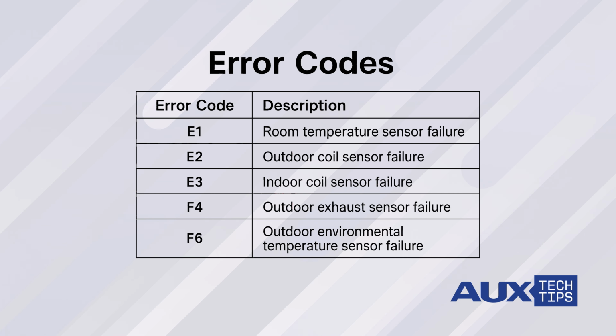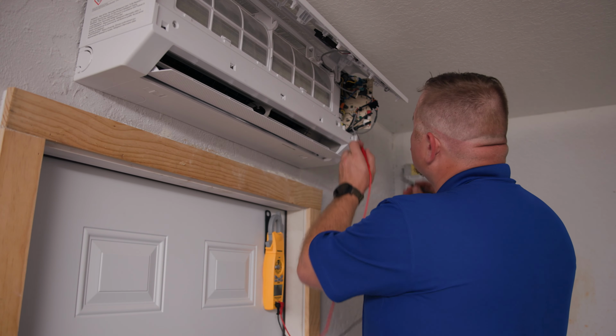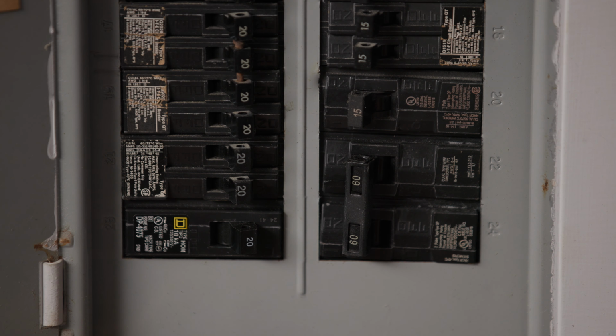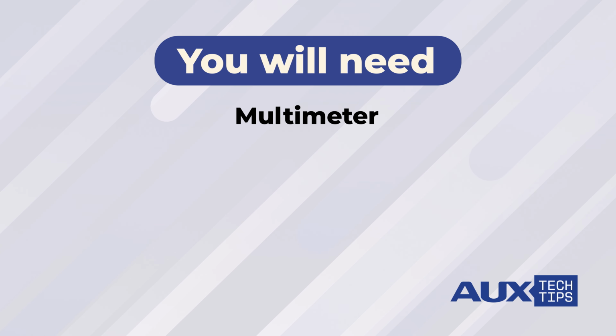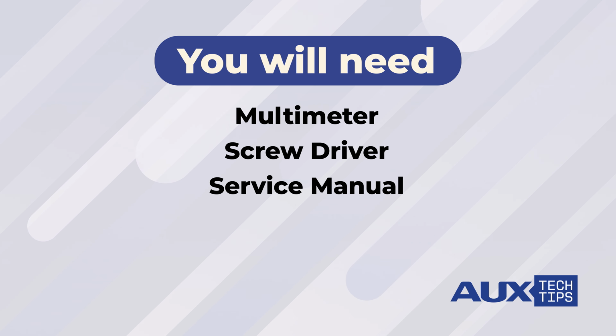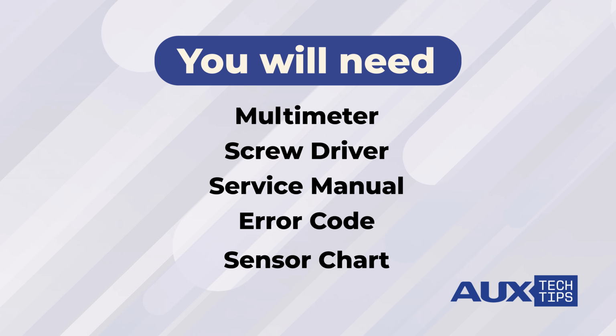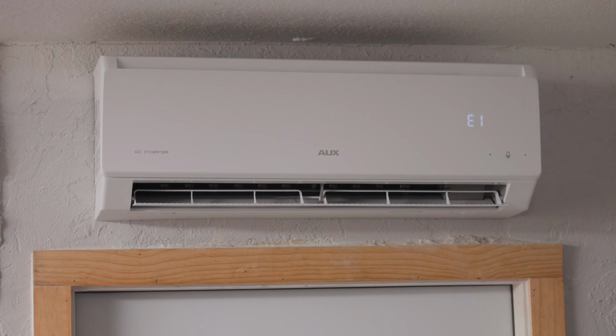To understand what the code identifies, check the sensor chart in the service manual. We'll test the thermistors with the multimeter to find any problems. Safety first. Always power off and unplug the AUX mini-split before you start. You will need a multimeter, a screwdriver, and your AUX mini-split service manual to confirm the thermistor's location, the error code, and the sensor chart for the resistance values.